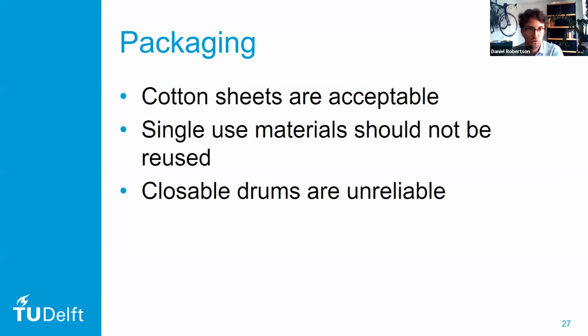Sometimes you have single-use packaging materials, and these single-use packaging materials should not be reused after they have been sterilized. The reason for this is that these materials become brittle after they have been sterilized the first time. And when they're brittle, they break very easily, and you no longer have a sterile barrier. The last common piece of packaging are closable steel drums. These closable steel drums are quite unreliable because as soon as they come out of the autoclave, they have to be closed, which means that microbes can enter them before you get the chance to close them.